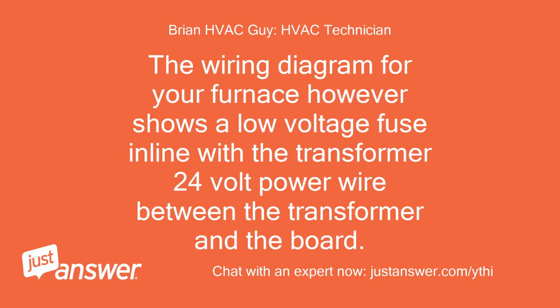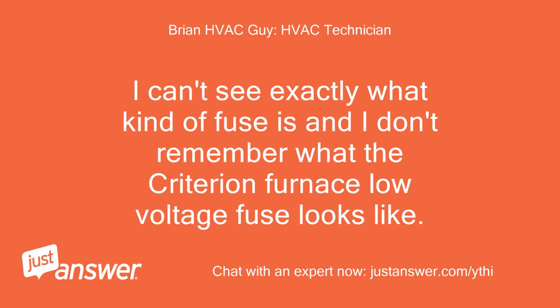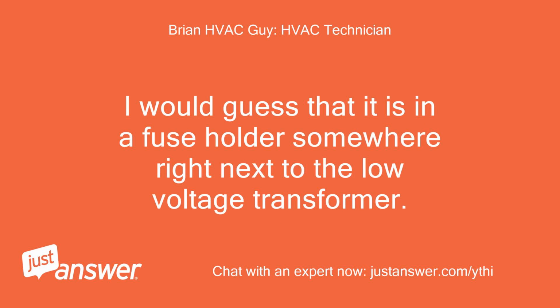The wiring diagram for your furnace, however, shows a low voltage fuse in line with the transformer 24-volt power wire between the transformer and the board. I can't see exactly what kind of fuse it is, and I don't remember what the Criterion furnace low voltage fuse looks like. I would guess that it is in a fuse holder somewhere right next to the low voltage transformer.